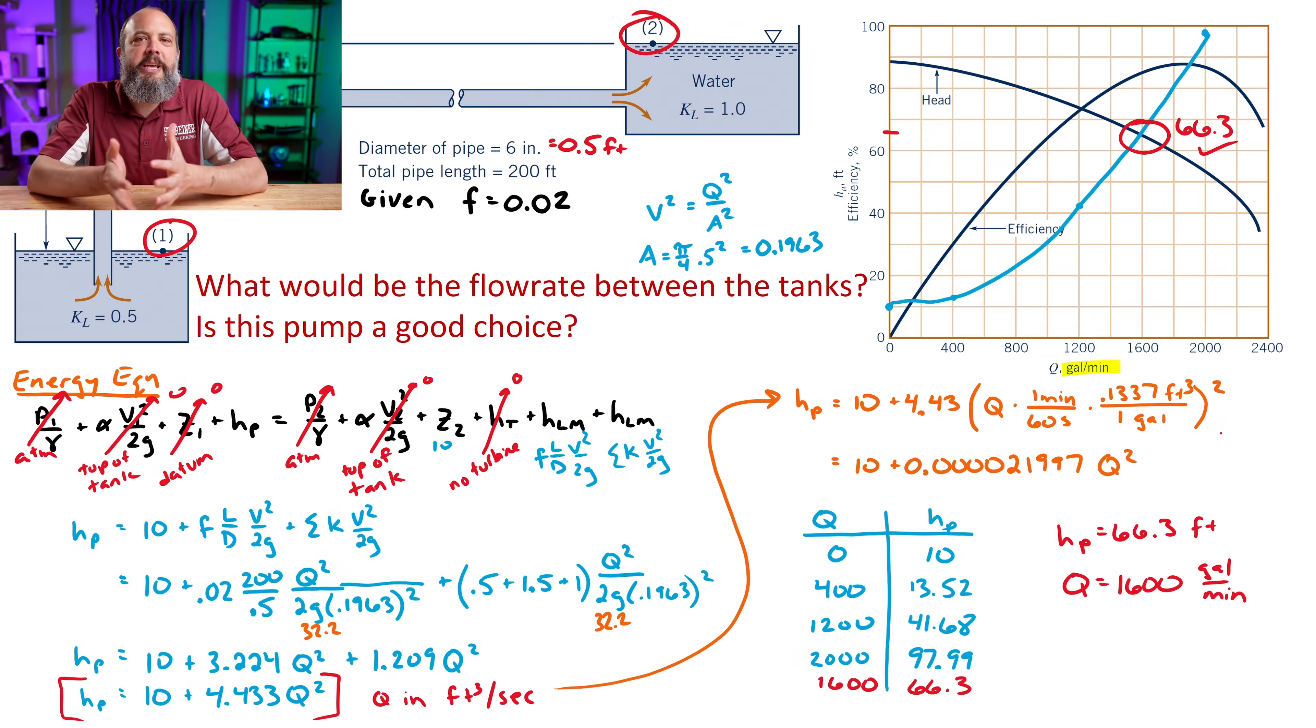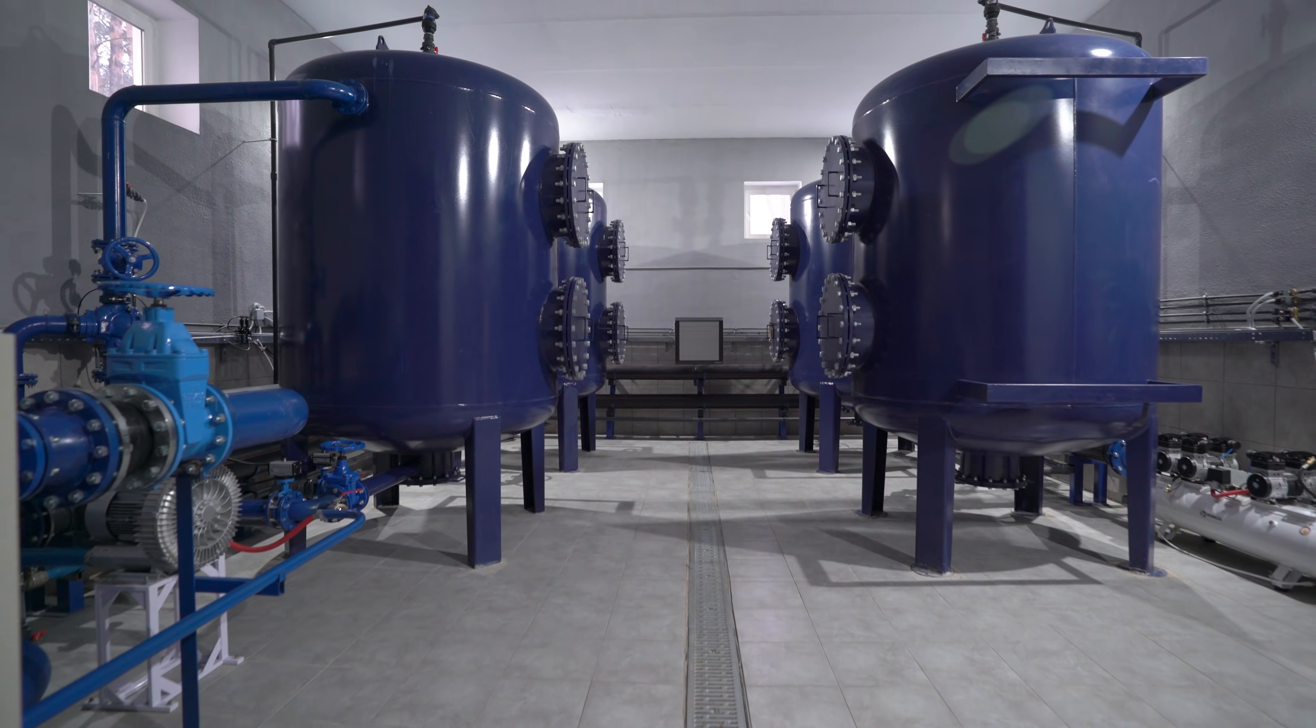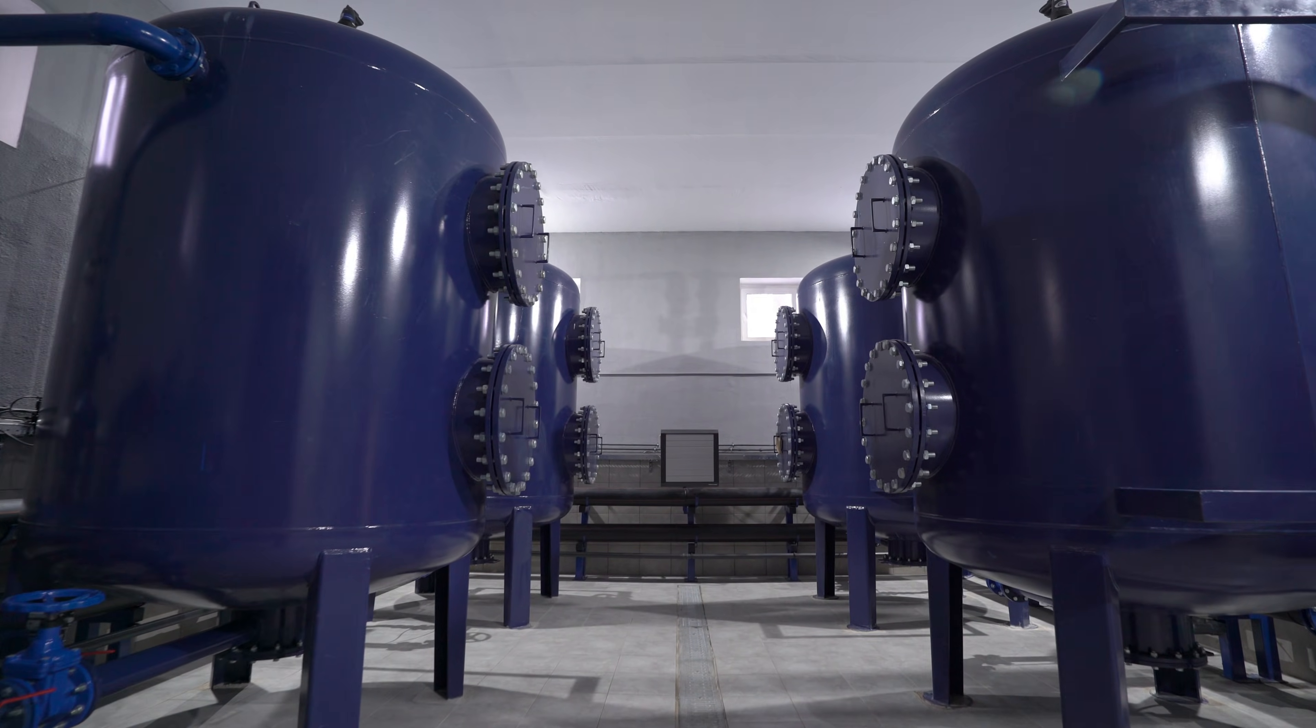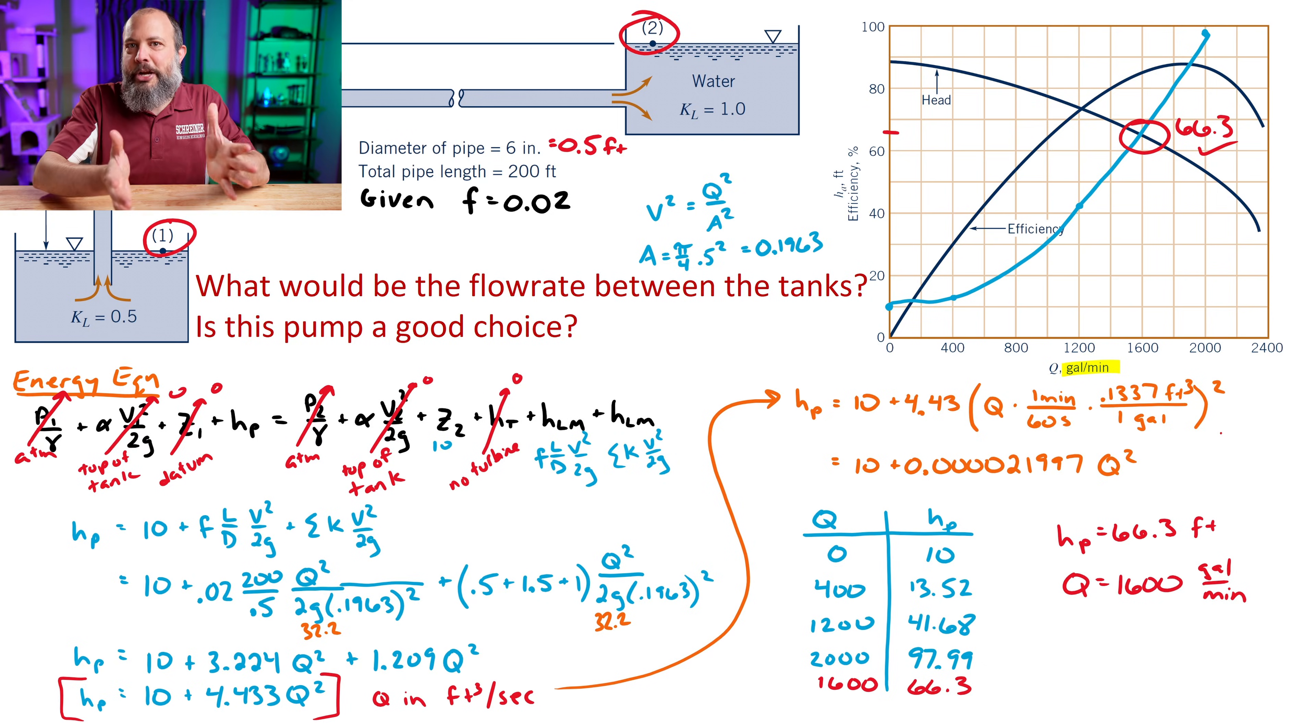So would this be a good choice of pump? Well, first thing is, is 1,600 gallons per minute fast enough? Like, is that enough flow rate for if we're pumping from tank to tank? Is that enough? It's one thing we don't know for this problem is whether 1,600 is actually going to work for the application. Like, are we time limited? Do we want to try to get this move from one tank to the other in a certain amount of time?